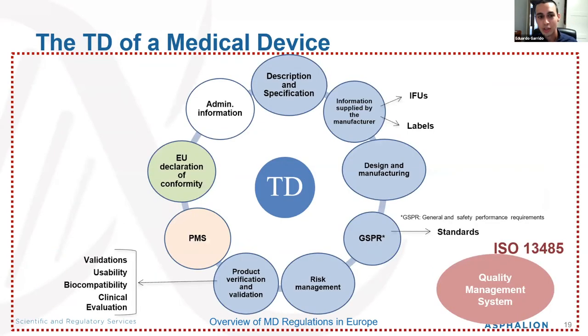So we were talking about this technical documentation. What is the technical documentation of a medical device? It's the core information that demonstrates you comply with the requirements. What should it include? You need a description and specification, and information to be supplied by the manufacturer — this means the instructions for use you provide to patients or users, and the labels included on the device.